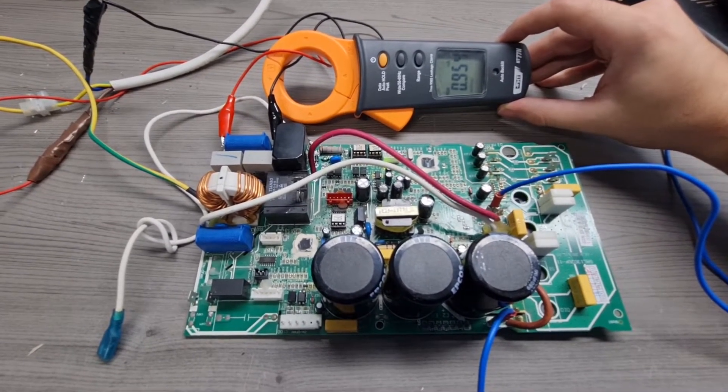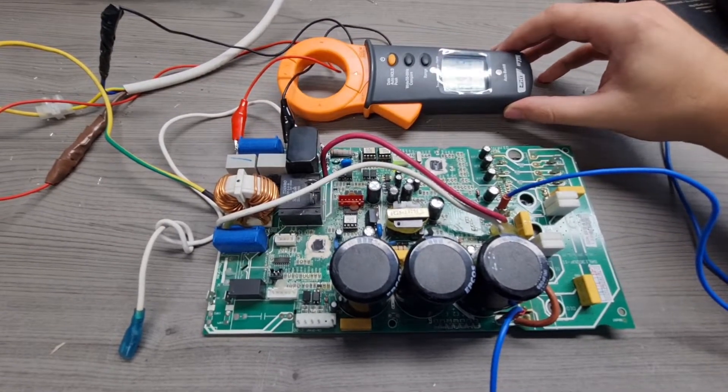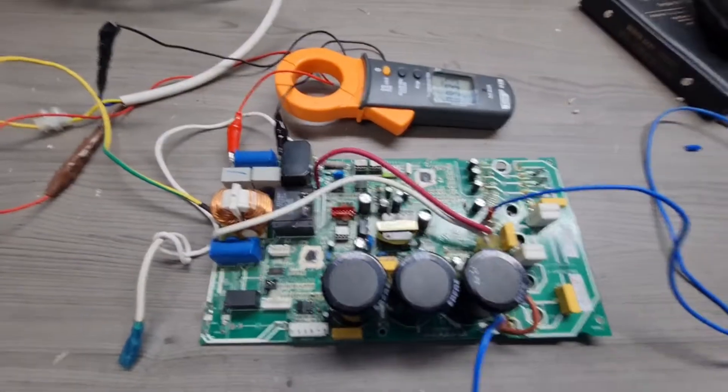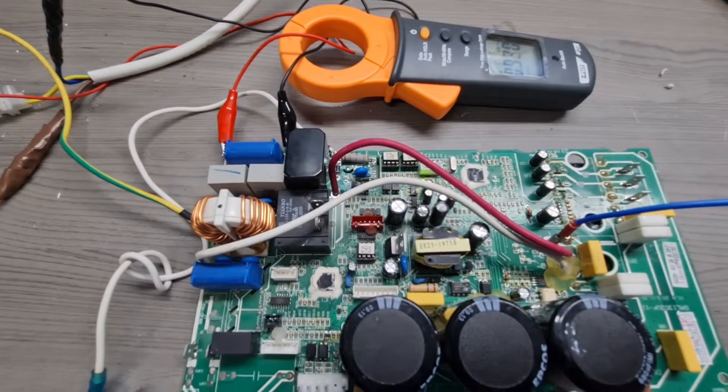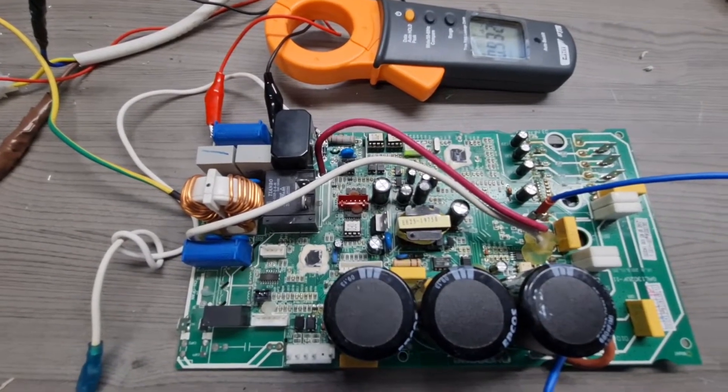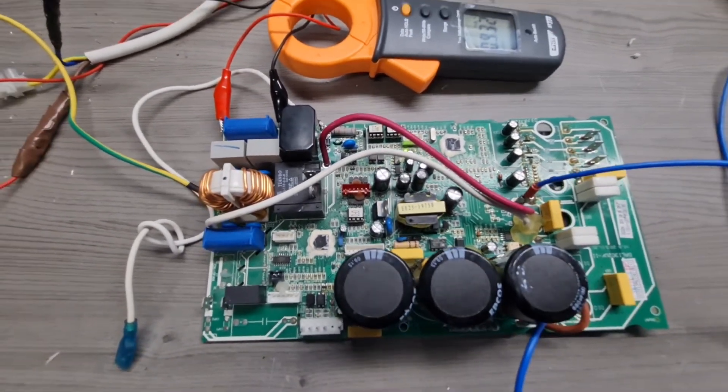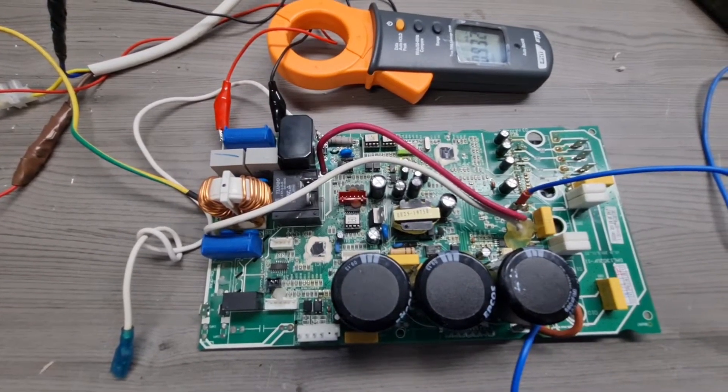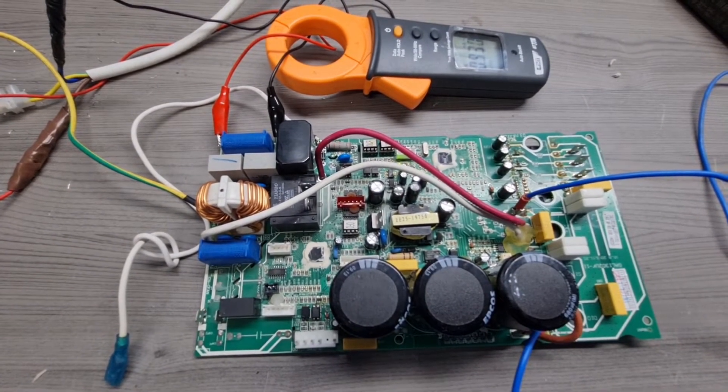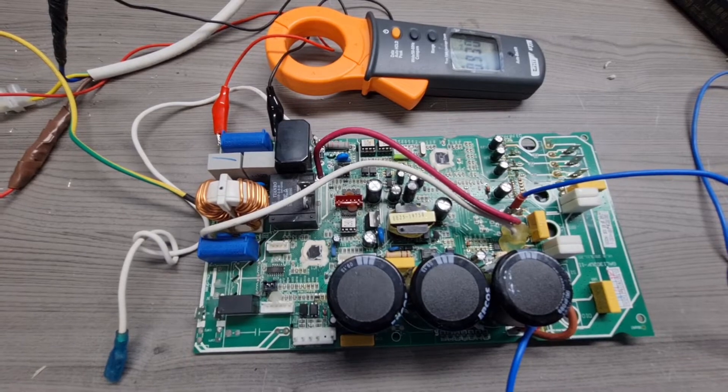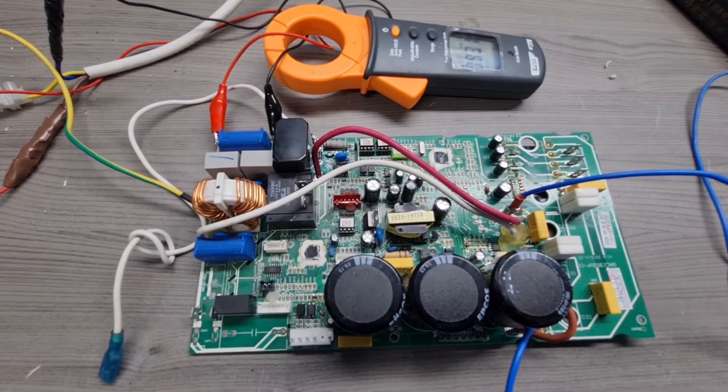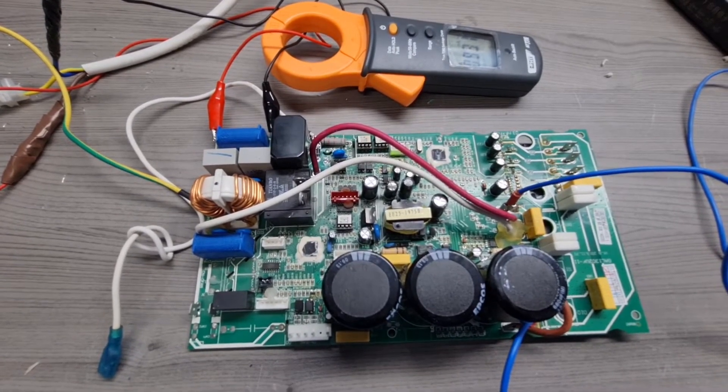So in this configuration we just have the power supply on as can be seen by the LED, and that is already giving me a leakage of 1 milliamp. Obviously this is expected to increase when we actually connect the fan motors and the compressor motors.